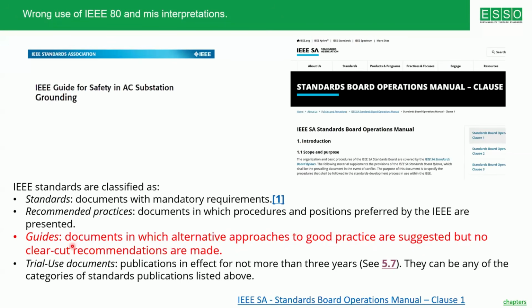First of all, please note that this is not applicable for an earthing system in a medical location or in a hospital. What I mean to say is, normally a fault current of 50 kiloampere, 65 kiloampere on the low voltage side of a transformer is asked for by the consultant. Says, I have two transformers, 2500 kVA, 1000 kVA, 50 kiloampere fault current is expected.